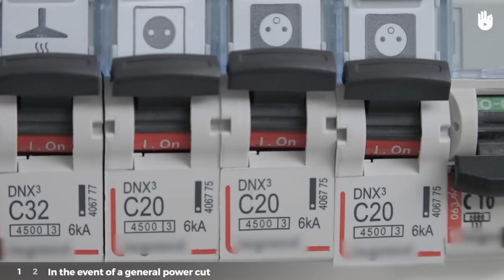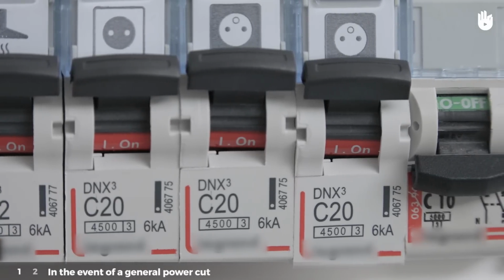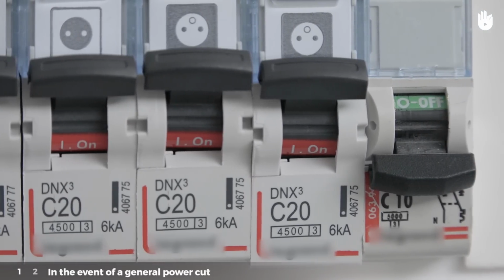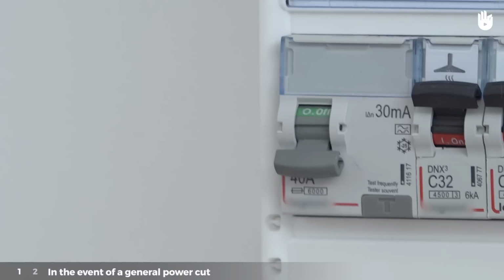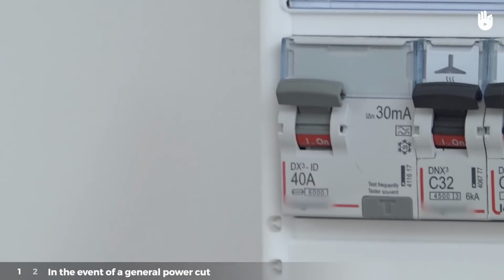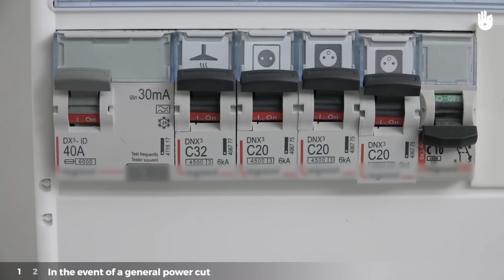Keep the protection system for the faulty circuit open in the down position. Turn the residual current protection system back on, then the other protection systems in the down position to use the rest of the system that is not faulty. The faulty circuit is now isolated. The specific cause of the fault can now be found.